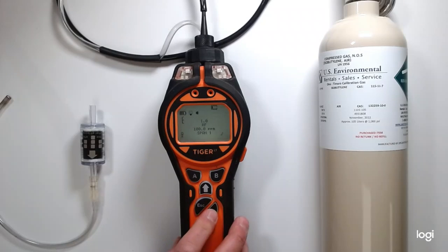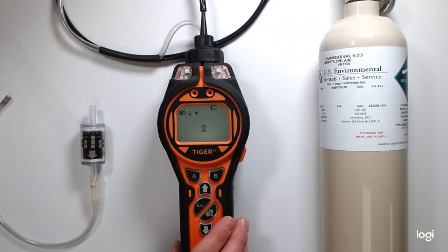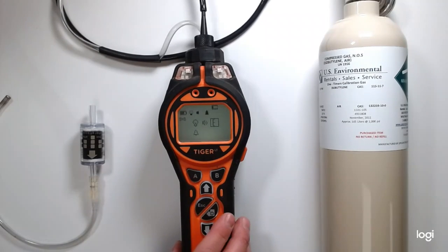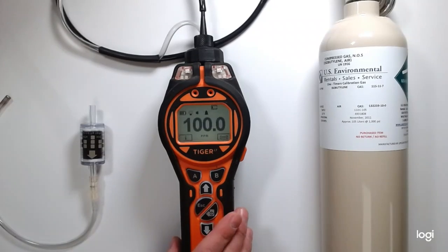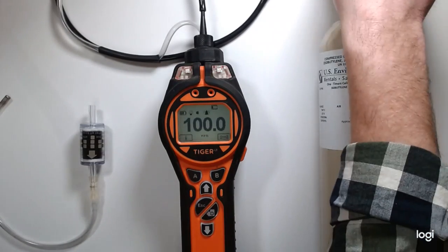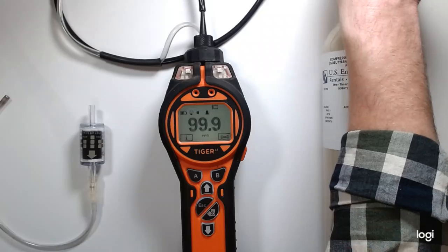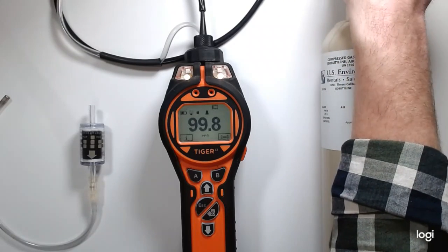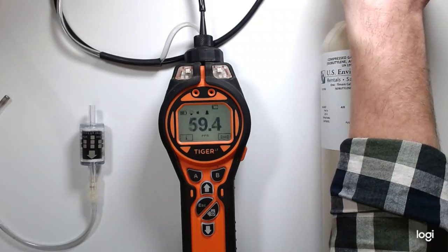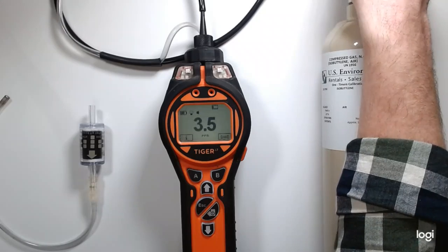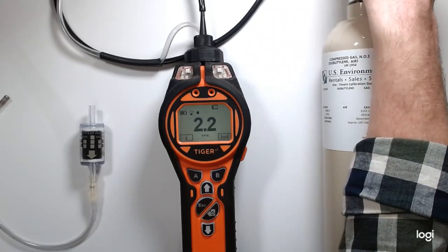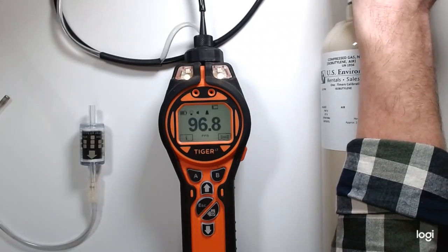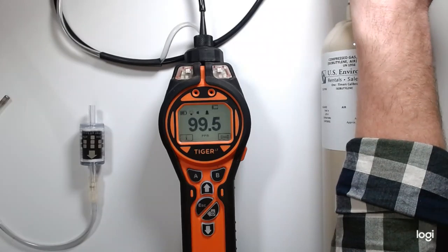Now that it's calibrated, we hit the enter button, and we're going to hit escape to go into run mode. We have 100. We're going to turn off our gas. Our reading should drop back down. We're going to turn it back on, give it a quick bump test. Should go back up to 100.